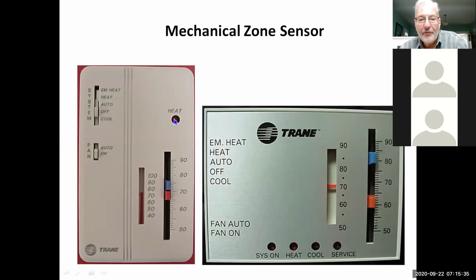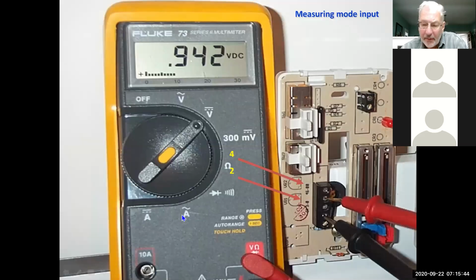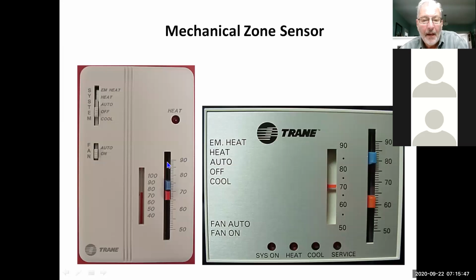Now, the old thermostats were 5 volt DC thermostats, and if you're working on them in the field, these are just potentiometer slides behind here. No, we're not going to show a picture of them, but a lot of times these will get grease, dirt or dust in them, and a real simple thing to do is take some contact cleaner, get in there and clean that up, and these slides usually just start working. The nice thing about these old controls is if the slides fail and they stop working, the unit usually just defaults to working off the sensor, and it'll maintain 71, 74. So if anything fails on here, it defaults back to standard operation on these rooftops.